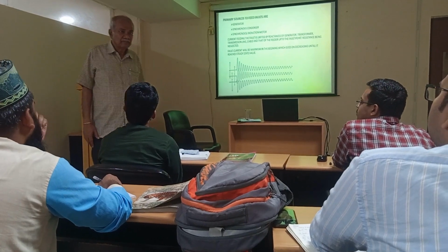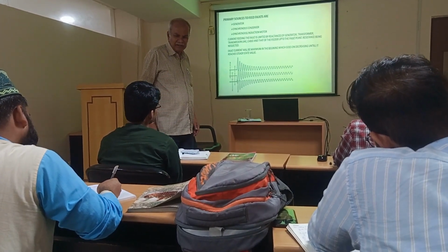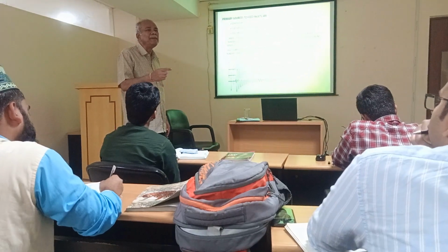Now you see, who feeds the fault? It is the generator, because that is the source. Transformer cannot feed anything because it does not generate anything. It only passes the fault current through it. It allows the fault current with a little bit of limiting because of its inherent reactance. Otherwise, it does not contribute anything to the fault current.